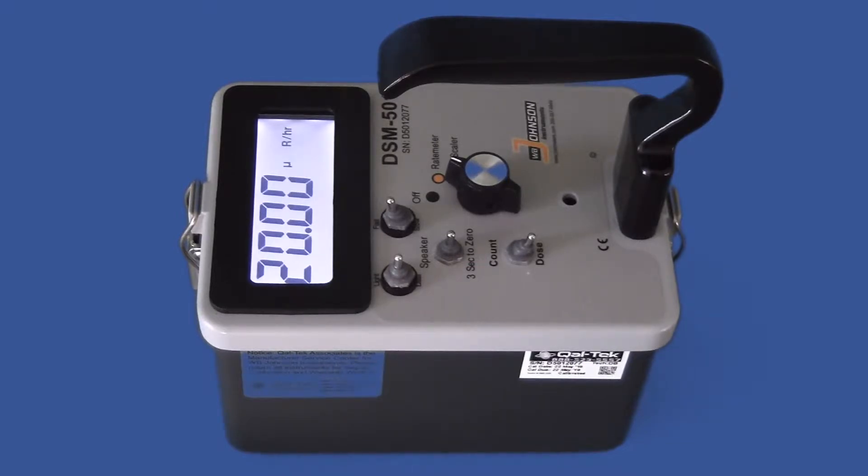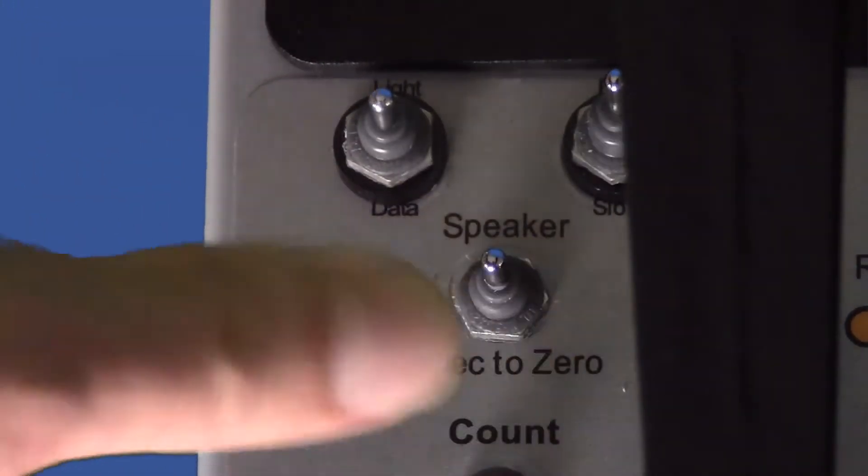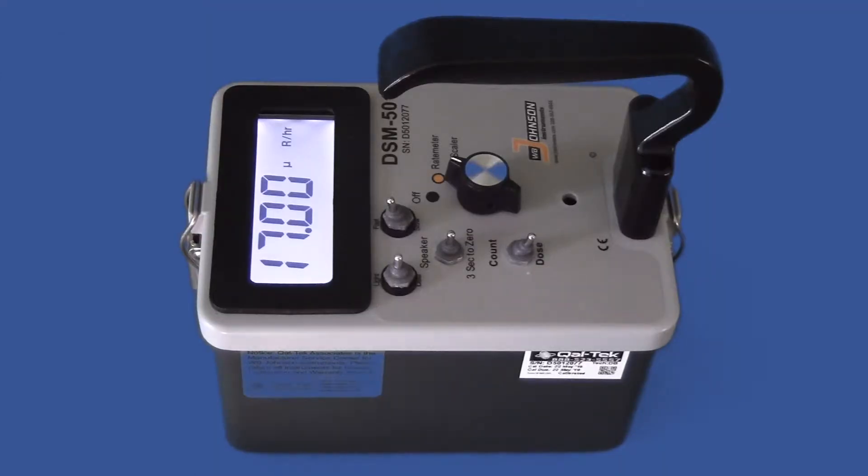We will now check out the speaker function. This switch toggles the speaker on and off. The speaker can respond faster than the meter display, so most keep it on during the survey, but it can also be turned off.